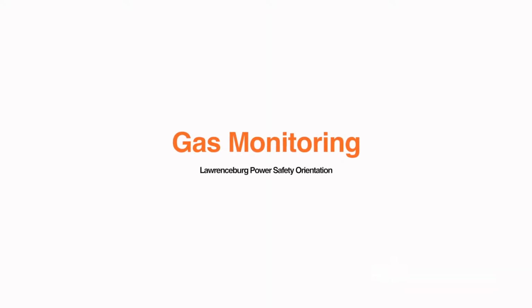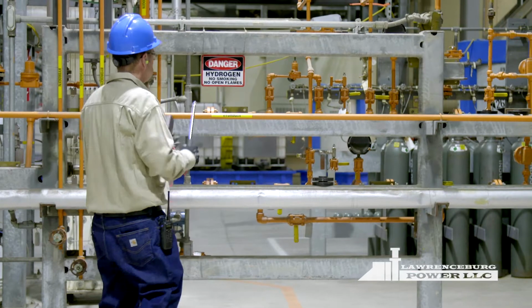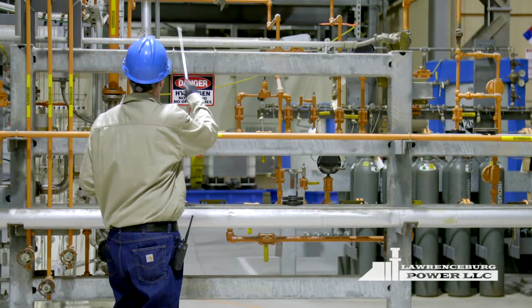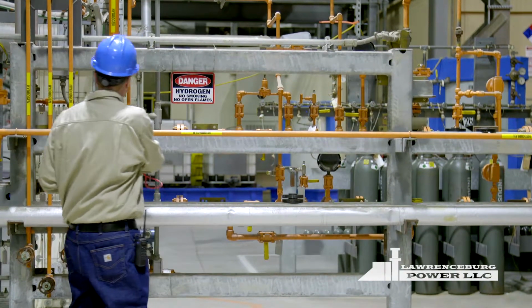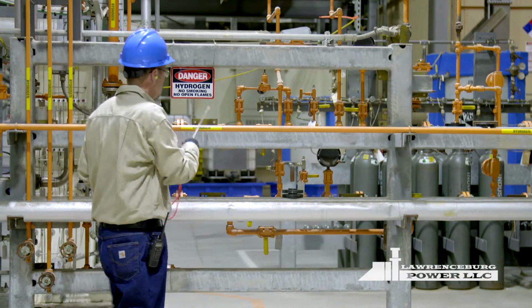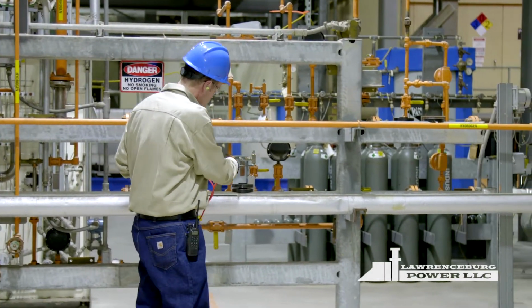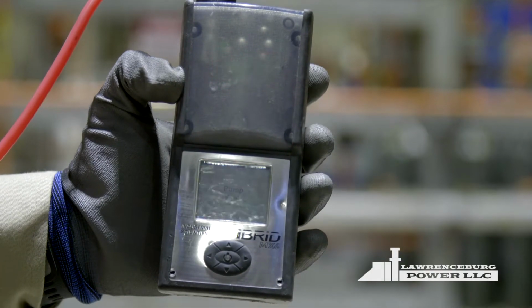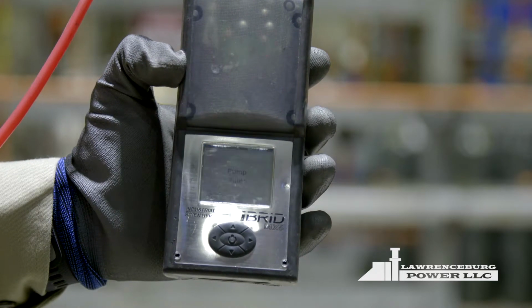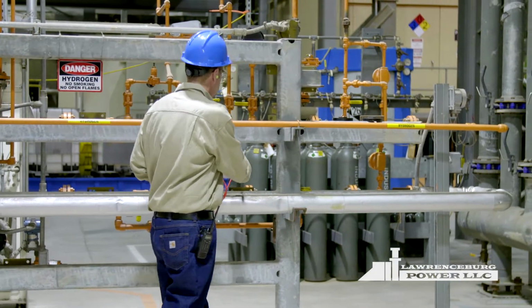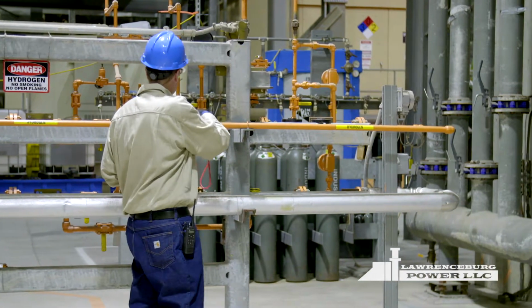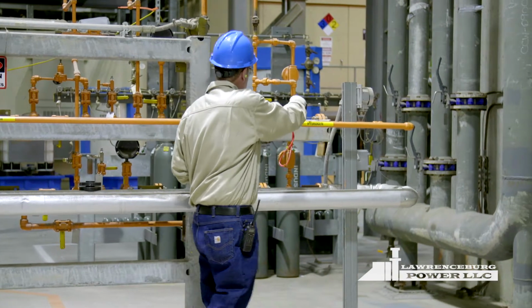Gas monitoring. For indoor sites, stationary gas detection devices are mounted near the ceilings to detect leakage and send warning signals. Portable gas detection devices are carried by personnel to monitor for leakage when working in hazardous areas or to mitigate the use of non-intrinsically safe tools or devices.